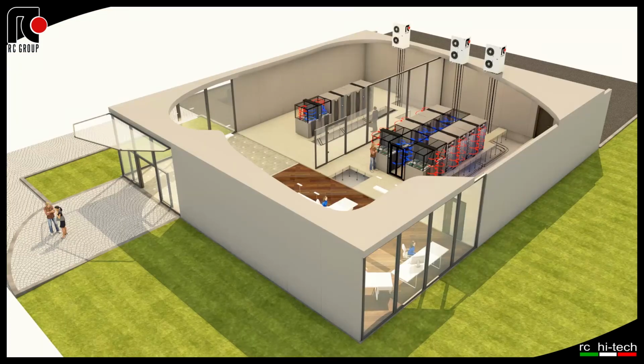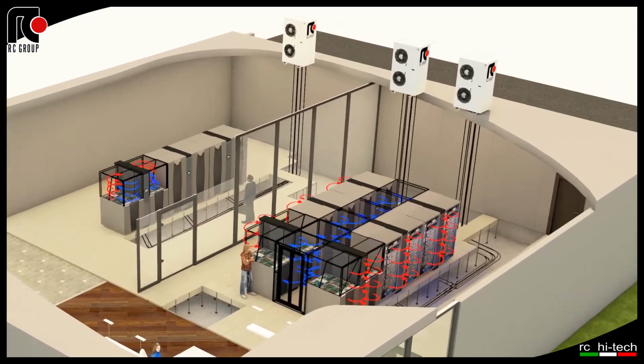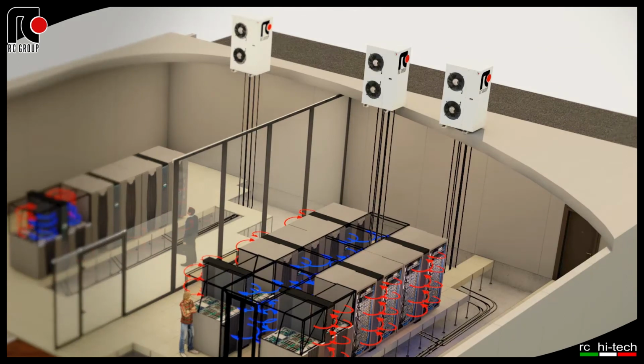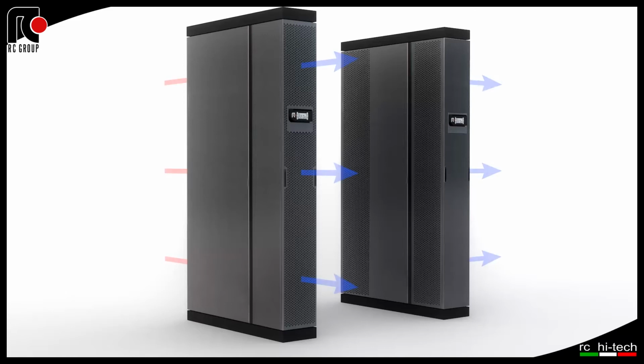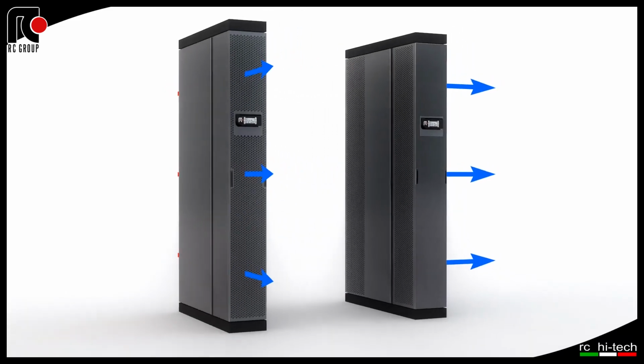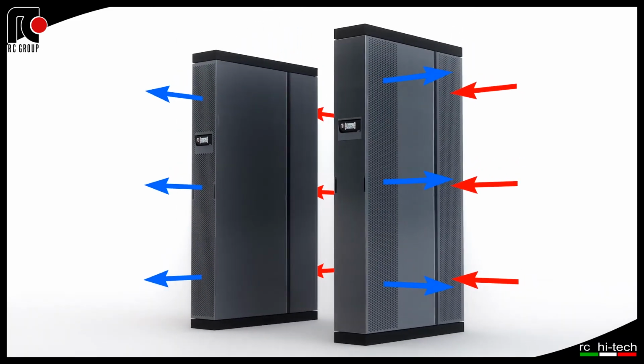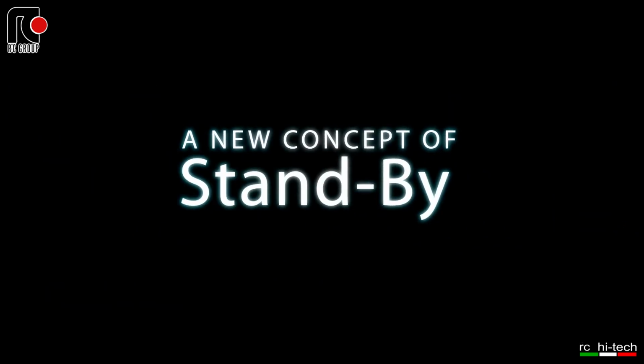Up to 3 indoor evaporator units can be matched to each single outdoor motocondensing unit, being complete with EC motor-type axial fans, inverter-driven scroll compressor, and aluminium-aluminium microchannel type condensing coils. The cool side indoor units are also available in a chilled water version for combining with one of the many types of RC Group liquid chiller options, a new concept of standby.